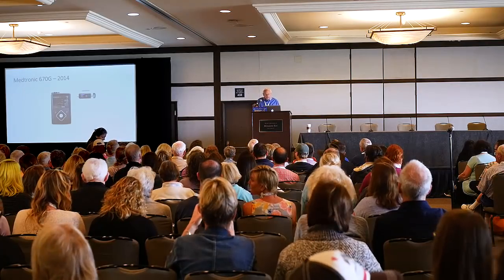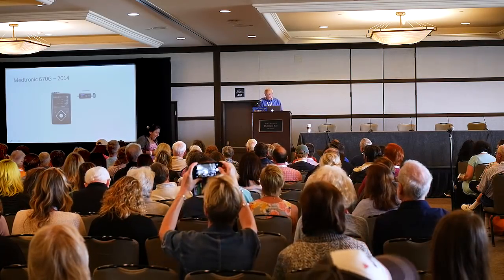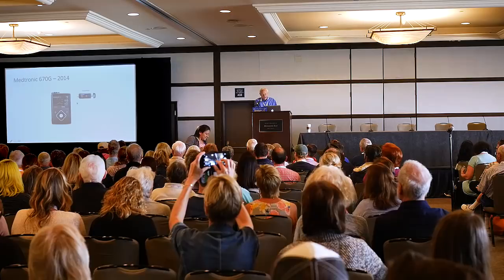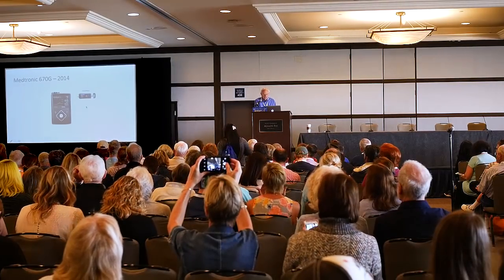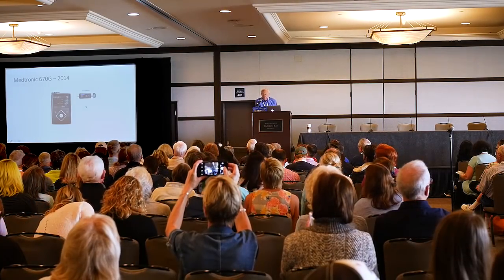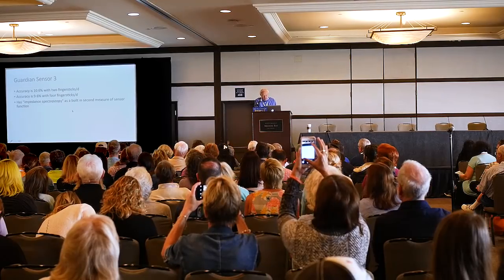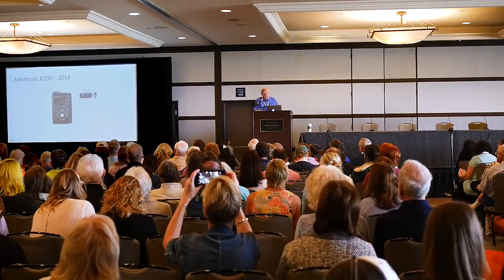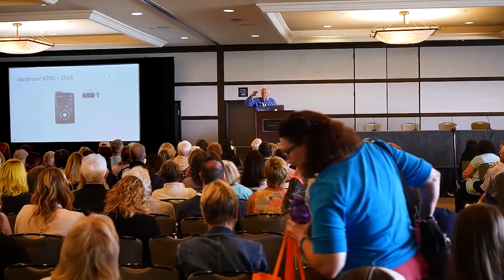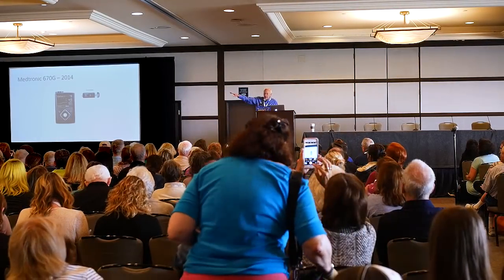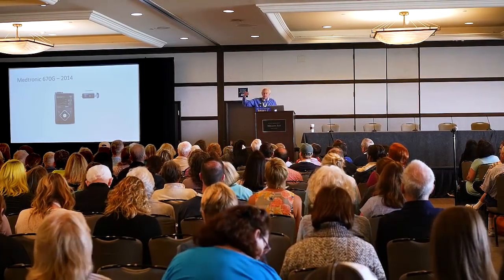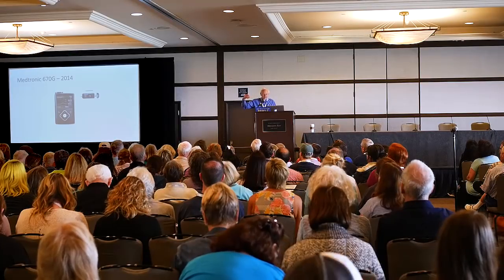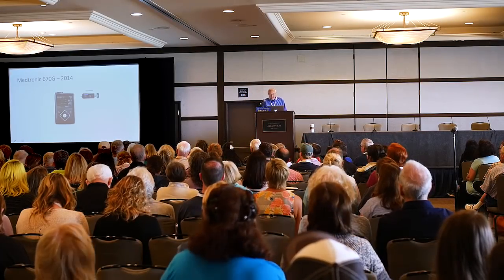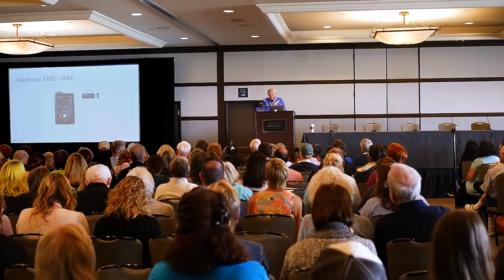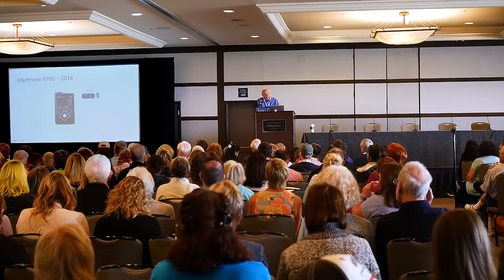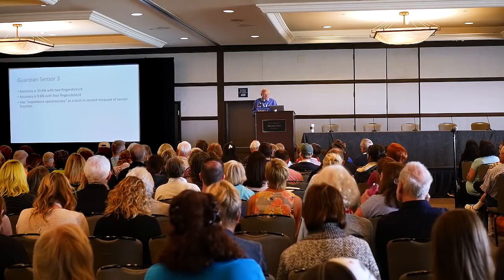I'm just going to go through this real quick. This is the 670G system. It has a sensor, a new sensor they've come out with, which has better accuracy. It talks to the pump, and the pump has the algorithm on it. It's a basal rate modulator, so it controls your basal rate for you. You don't program a basal rate into this pump when it's in auto mode. This is the meter, which talks to the pump. This is when it's in open loop, and I'll show you some pictures of it in closed loop.